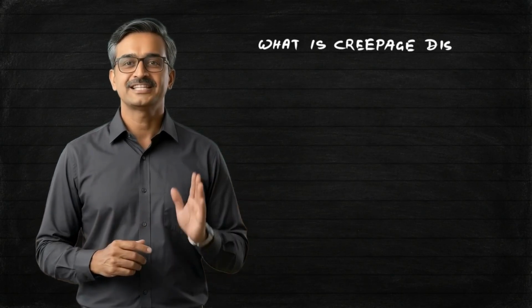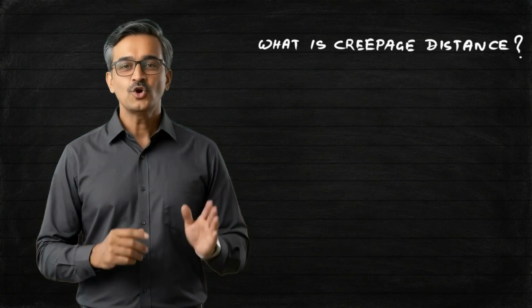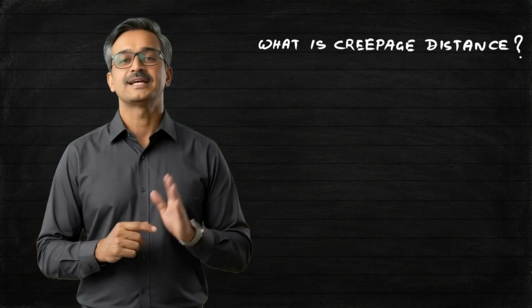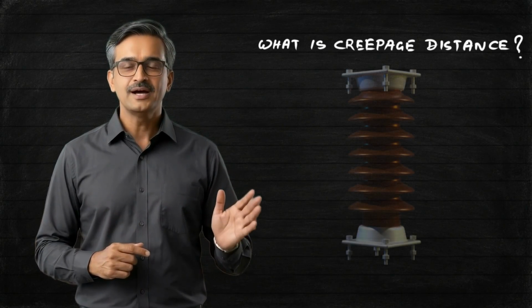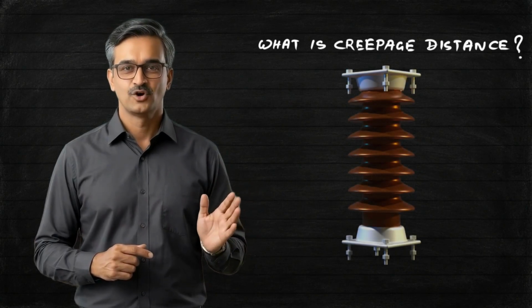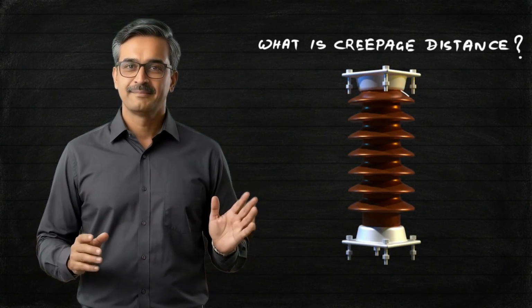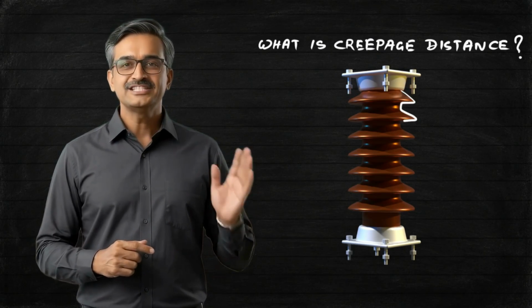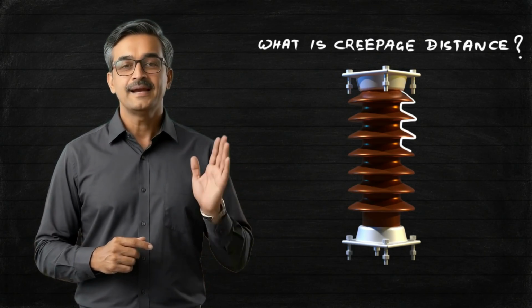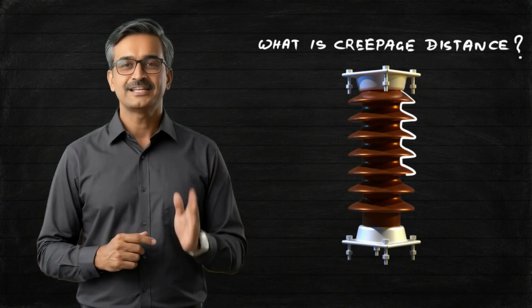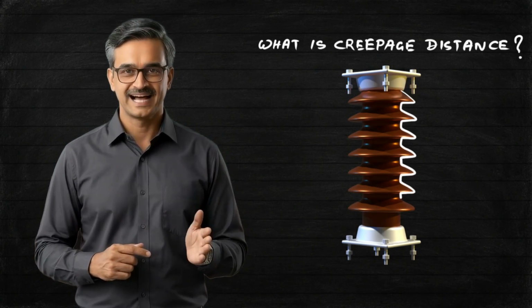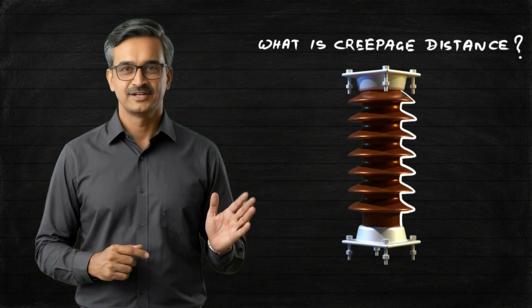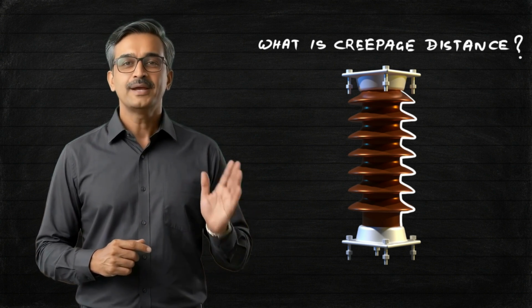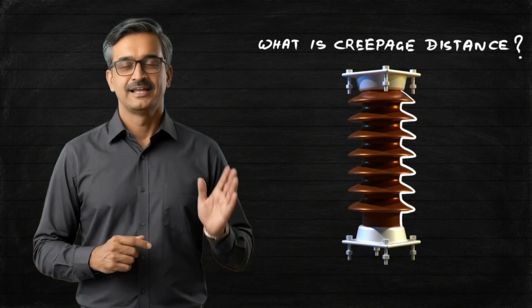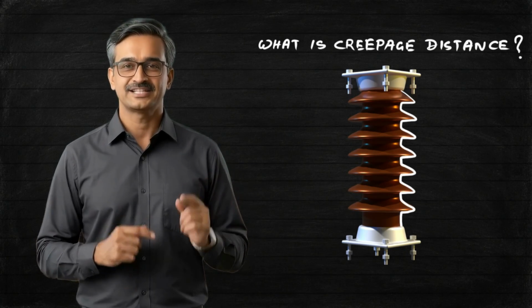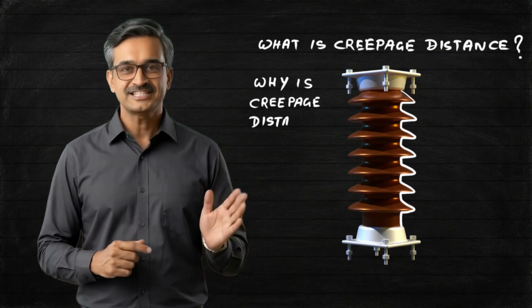What is creepage distance? Creepage distance is the shortest distance measured along the surface of an insulator between two conductive parts. Remember, this is not the straight line distance through air. Imagine an ant walking from the energized terminal to the grounded metal fitting, following every shed and rib of the insulator. The distance traveled by the ant is the creepage distance. The longer this path, the more difficult it becomes for leakage current to create a continuous conducting path over the insulator surface.